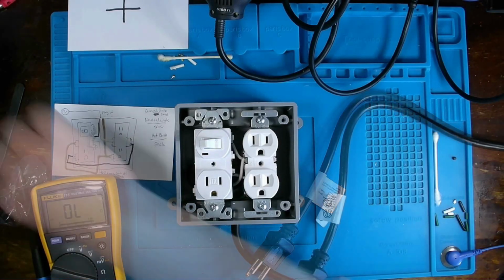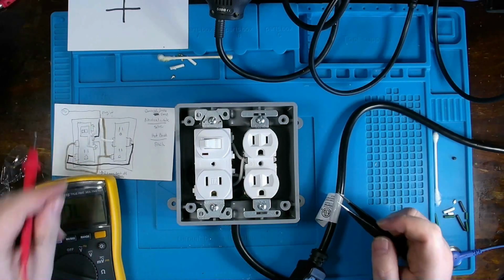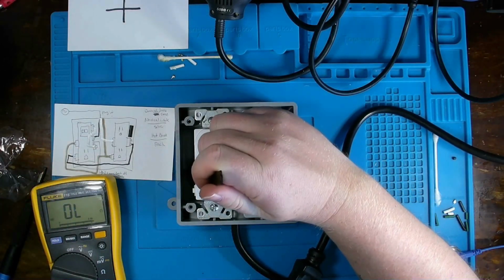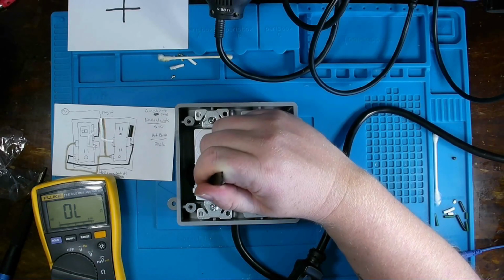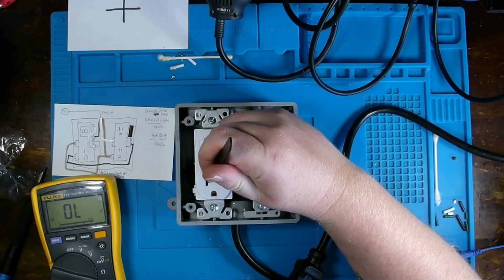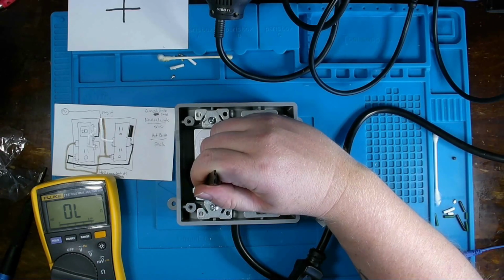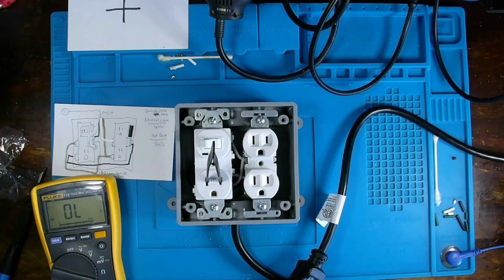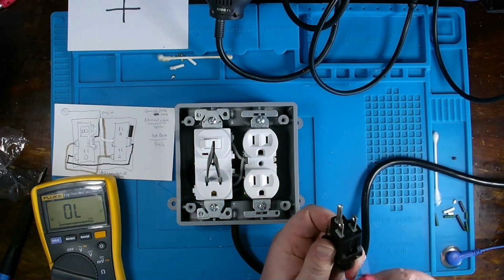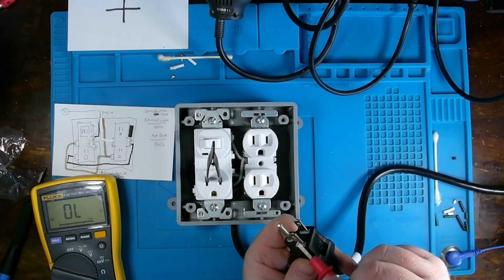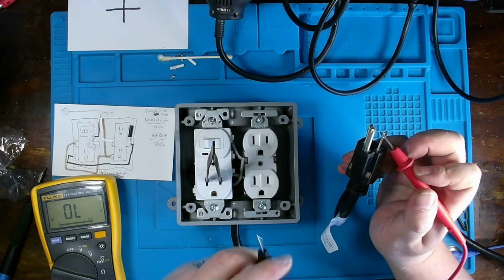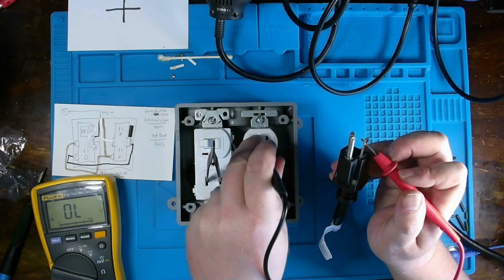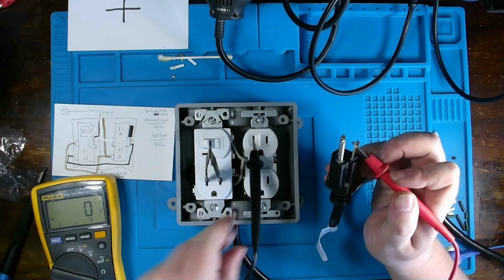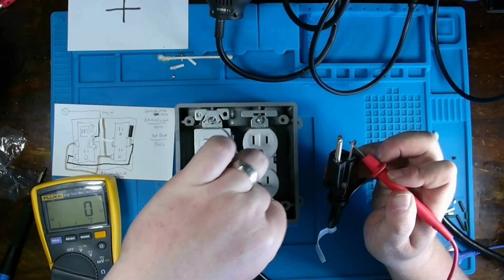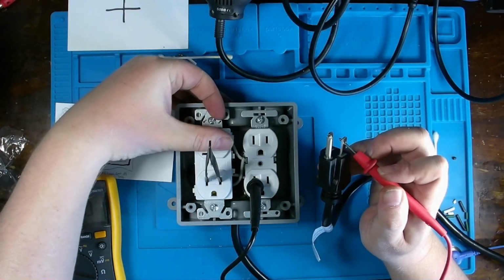And I do. The next thing I need to do is check my neutral. I'm going to try to use these tweezers, put down to this receptacle. Probably not the best way to do this, but it is the way I'm choosing. Okay, hopefully that's shorted out. Now I need to be able to test from the neutral lead, that is this side right here to here, and I should get continuity. And I do. Also with this test, no matter the switch in the off or on position, my neutral should always be connected.